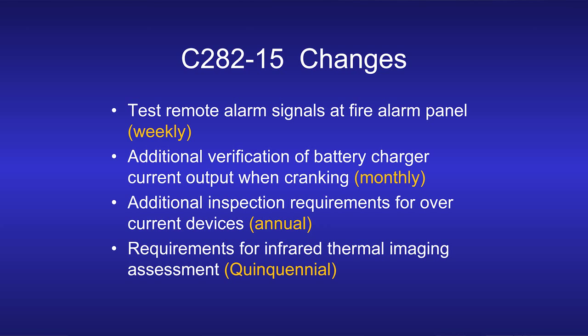Now, as of the 2015 edition, we have to do infrared thermal imaging. Before, we were coming with a heat gun and taking quick measurements to see if there were any alleged hot spots. Now we have to take a picture with a thermal imaging camera every 5 years. That's a more extensive and invasive approach, but it gives you a picture record of what was seen at the time of the inspection. And when the fire department comes in to check your records, you can show them all these pictures. They are to be stored with the rest of the reports.